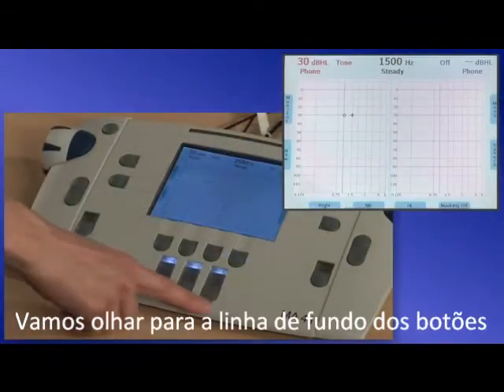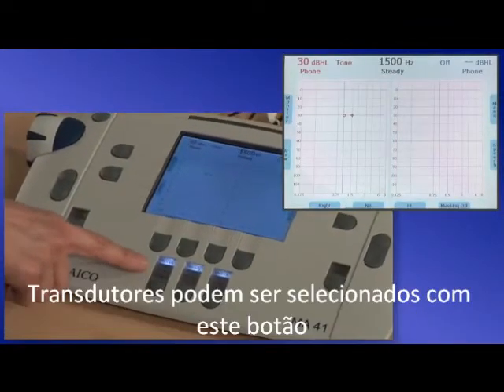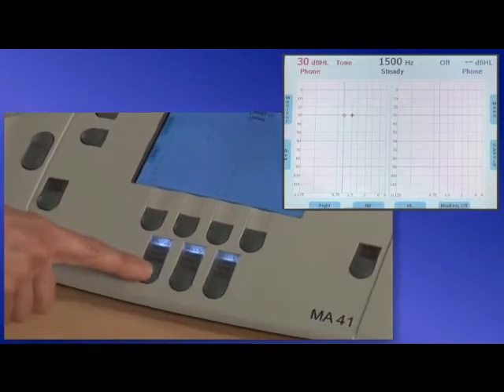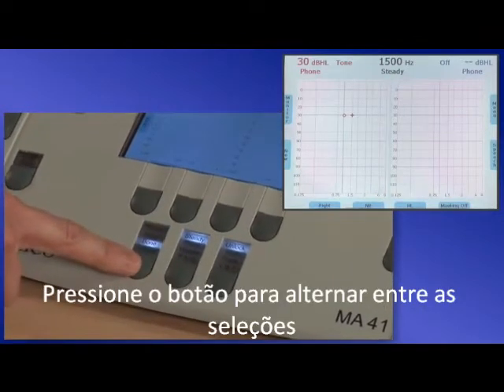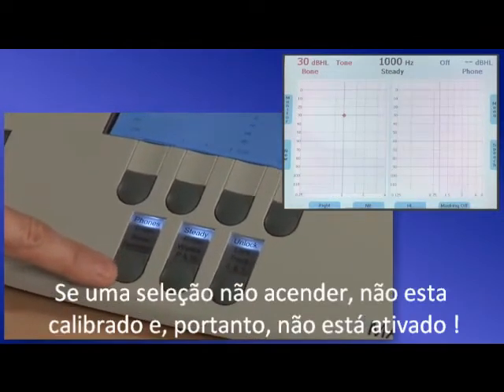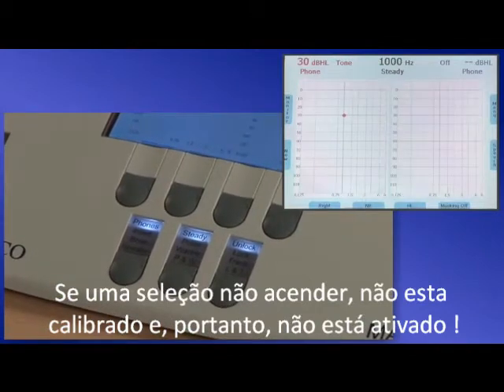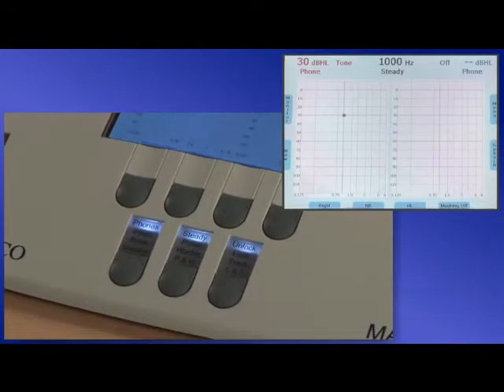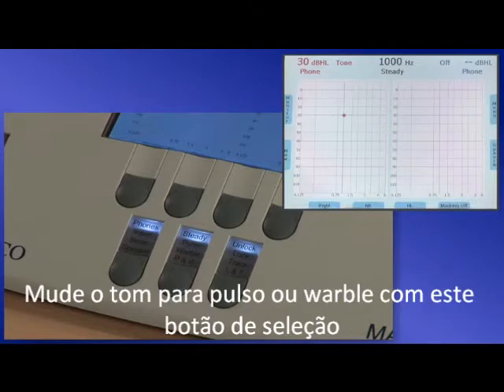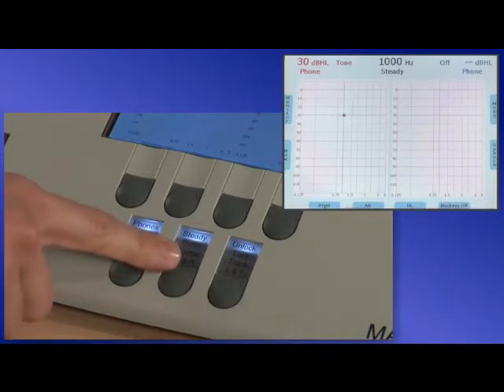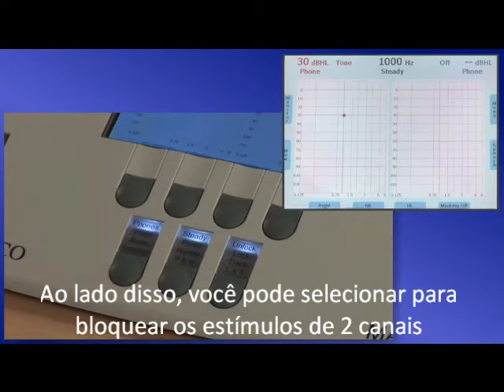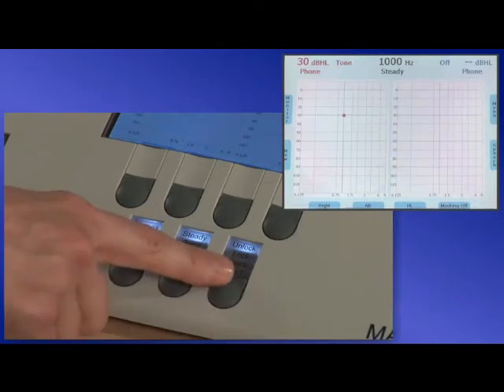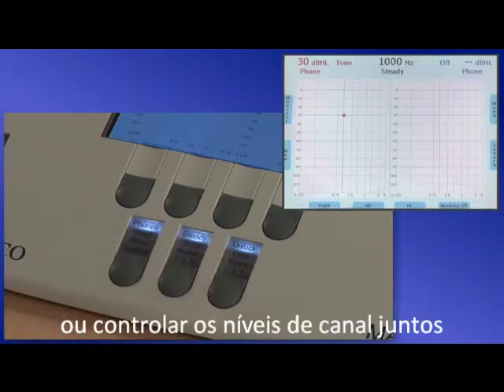Let's look at the bottom row of buttons. Transducers can be selected with this button. Press the button to toggle through the selections. If a selection does not light up, it is not calibrated and therefore not activated. Change the tone to pulse or warble with this selection button. Next to that, you can select to lock the stimuli of the two channels or track the channel levels together.